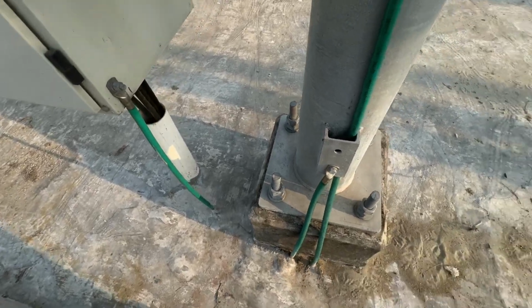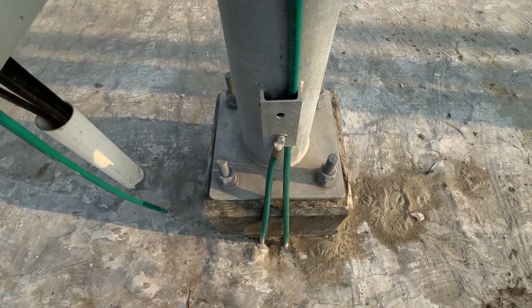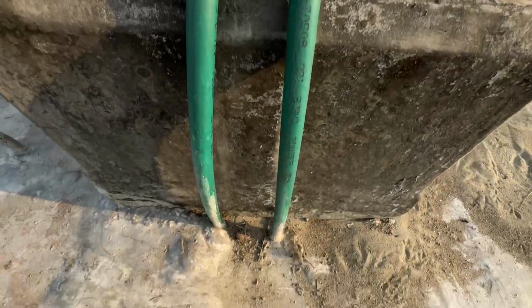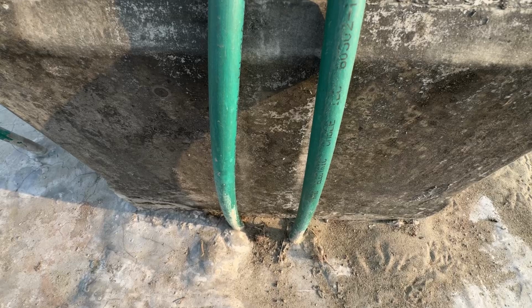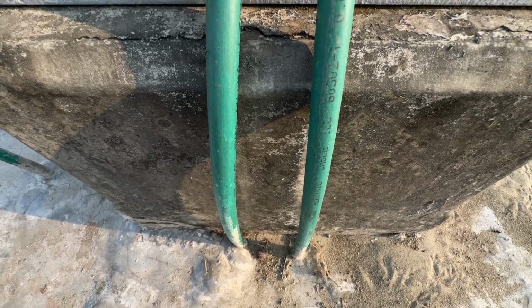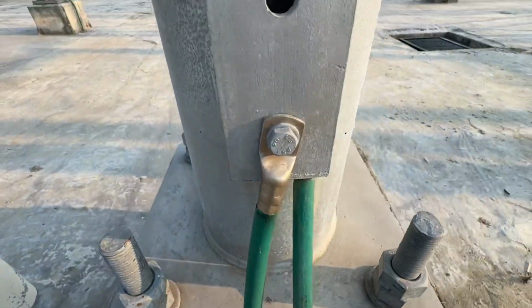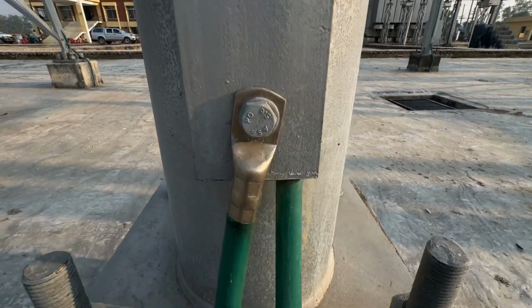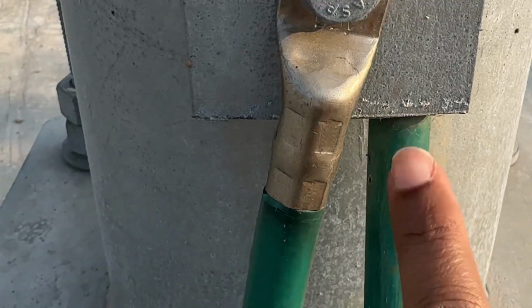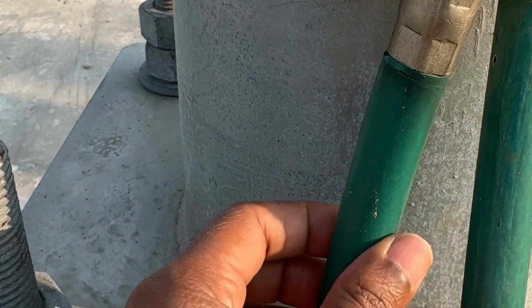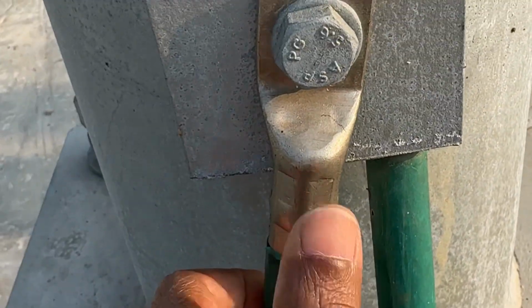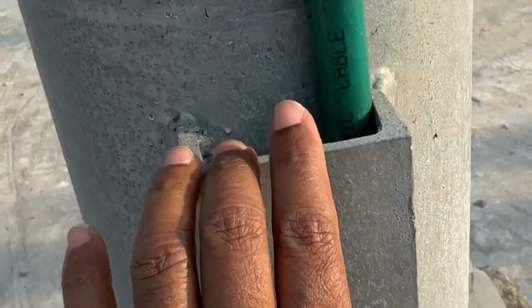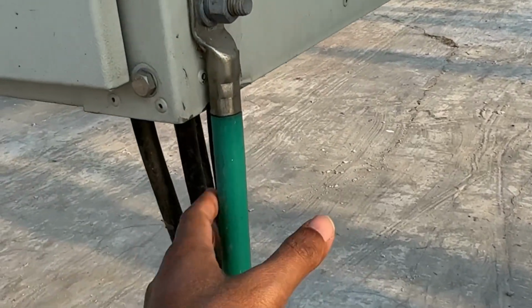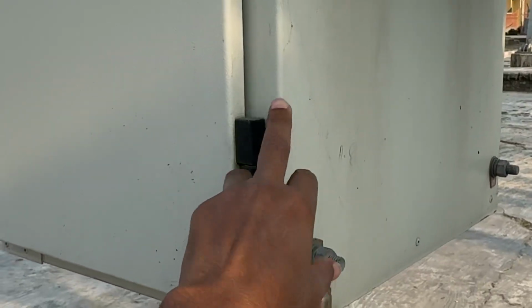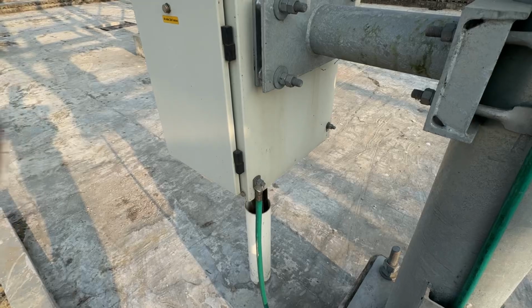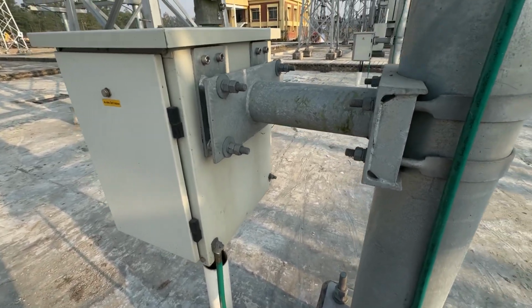These are the substation earthing, secondary structure earthing. This is a ground conductor. It is connected through a mesh with the gantry structure. This is a cable lug. This is a copper conductor, insulated with PVC, and the lug is connected with the structure. This is also another earthing. It is connected with the operating mechanism of the isolator.